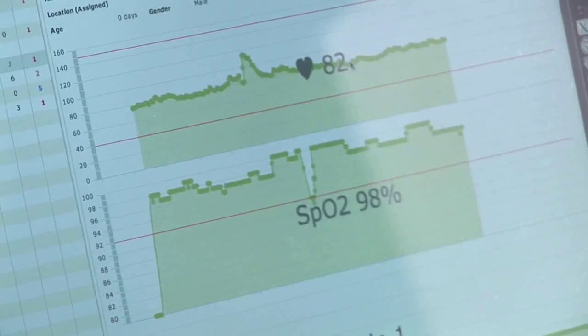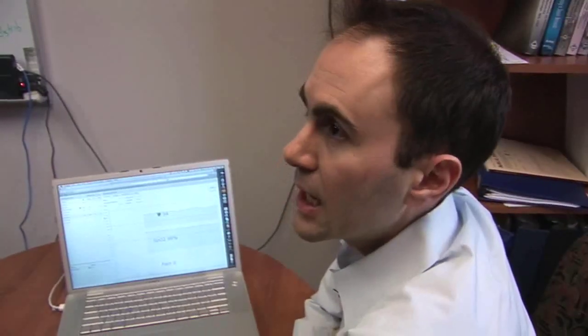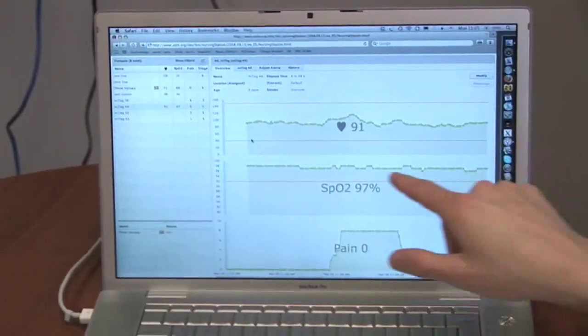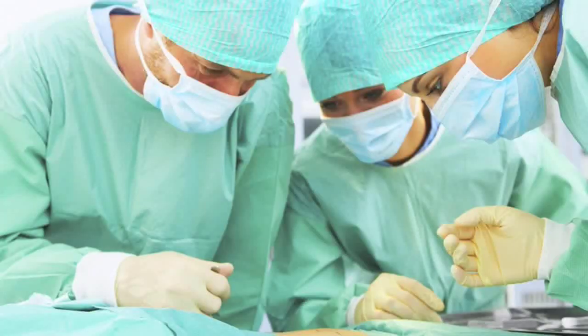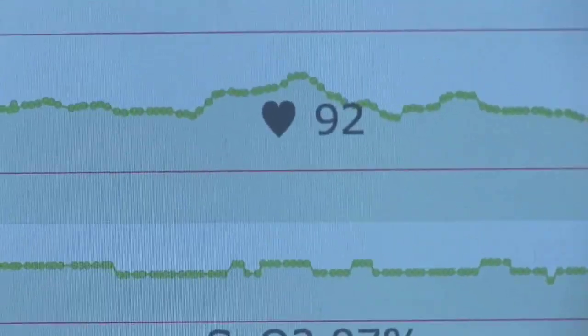These two metrics give a broad indication of a patient's health. When the heart rate goes above a certain threshold — below 40 or above 150 — both an audible and a visible alarm will be generated, so the nurse can very quickly see which patients are not feeling well.